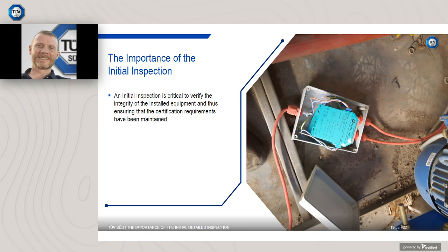This installation in the photograph had never been independently inspected. The uncertified junction box located in a hazardous zone contained barriers for an IS system. No IS loops existed. No IS earthing was evident. It was potentially unsafe.